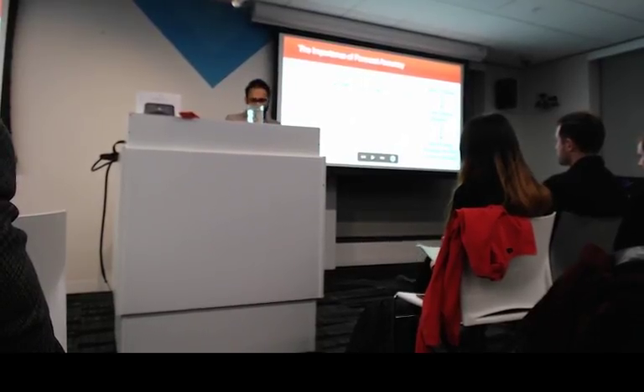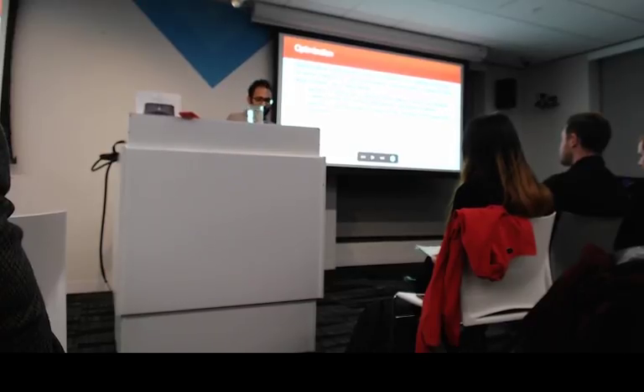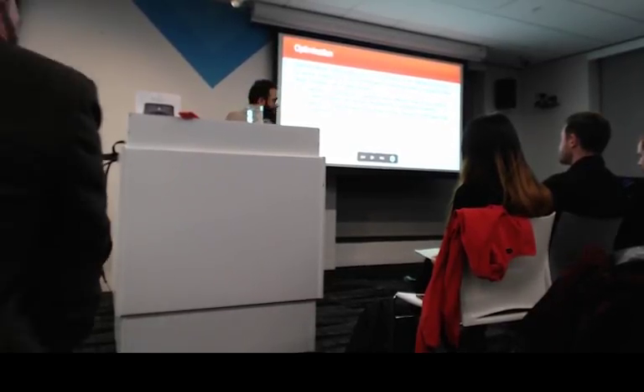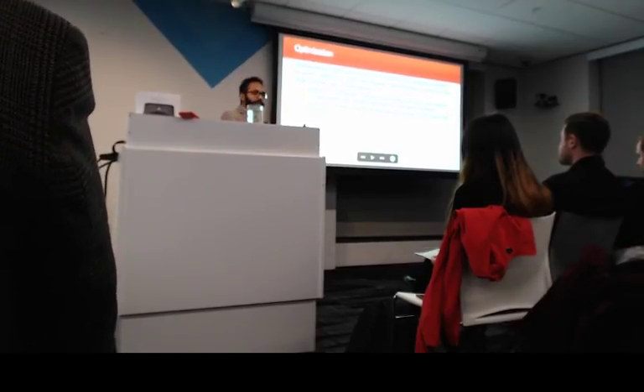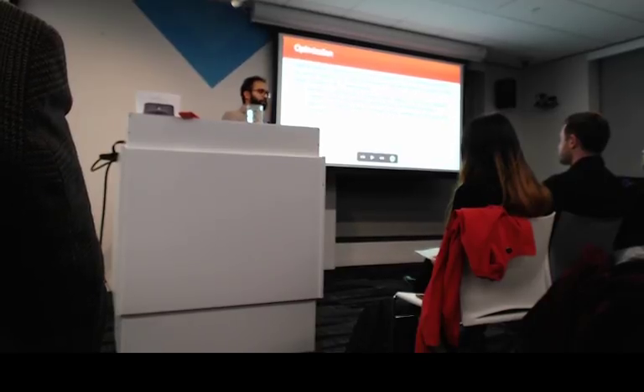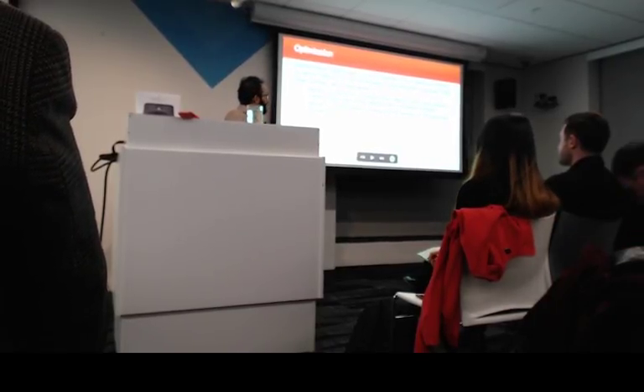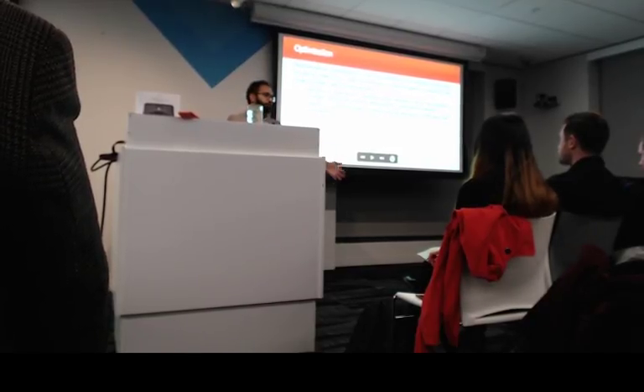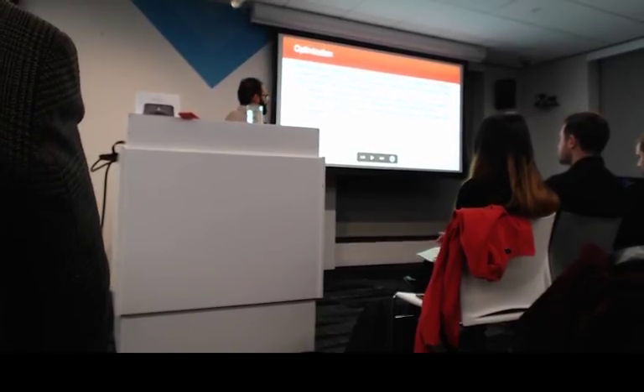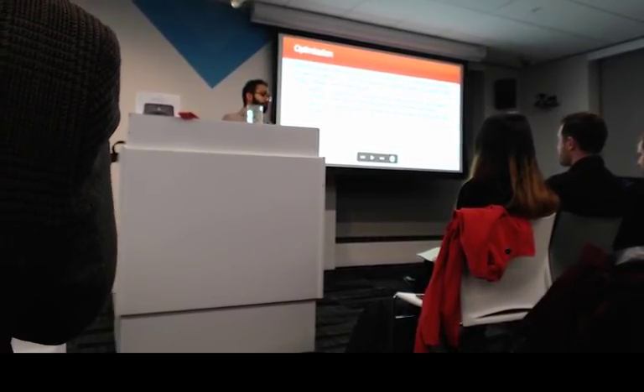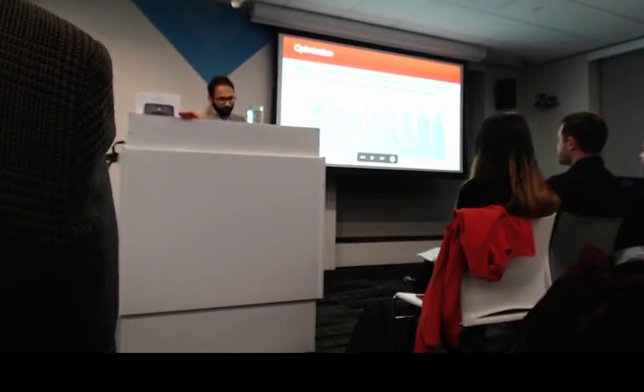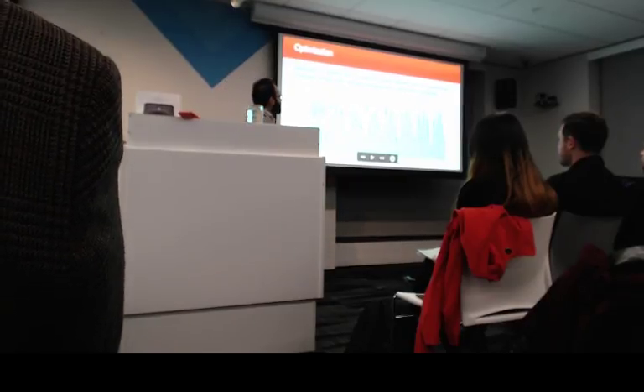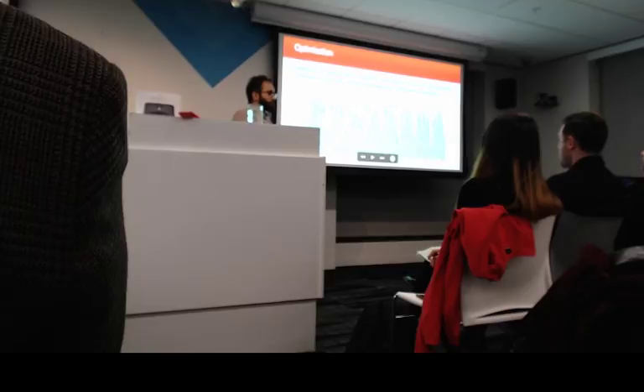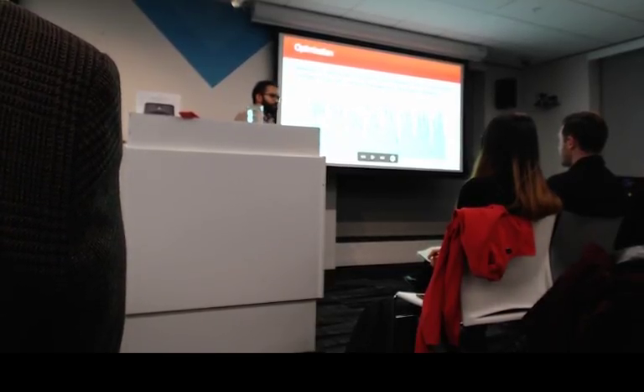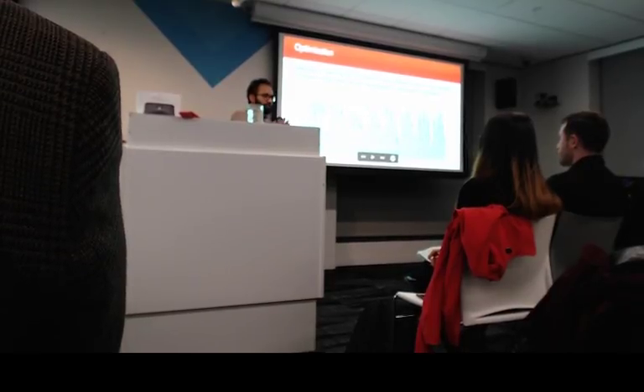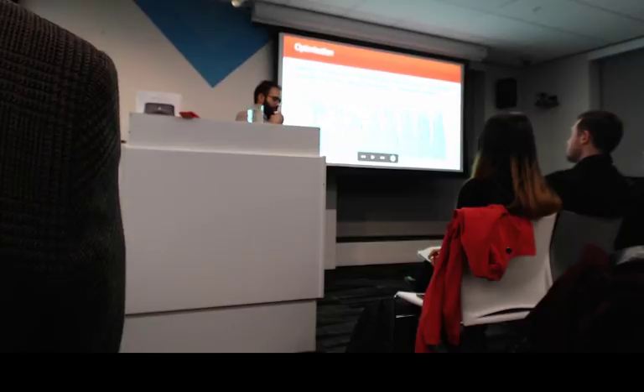Instead of doing this brute force approach, you could use one of these optimization frameworks. What they basically allow you to do is set a target or a cost function. So you want to minimize some function, and usually for us, it's minimize the cost to the customer, however you want to define that, and it's subject to some constraints, right? The battery can only discharge so much energy, it can only discharge at a certain rate, and in California you can't discharge out to the grid, so that could be another constraint, et cetera, et cetera. And then this is an example of one of our systems that just does demand management, but also is responding to a pretty interesting tariff called CPP, critical peak pricing. So at certain times when there's stress on the grid, the utility will call a CPP event.